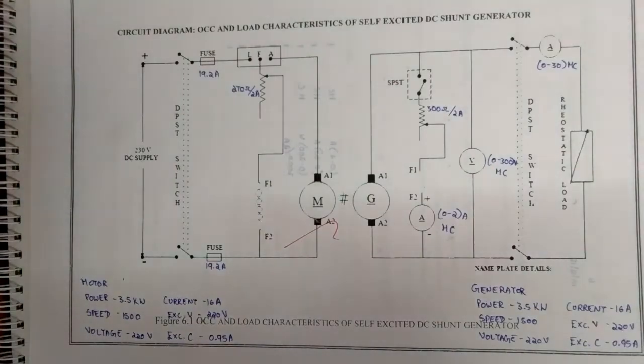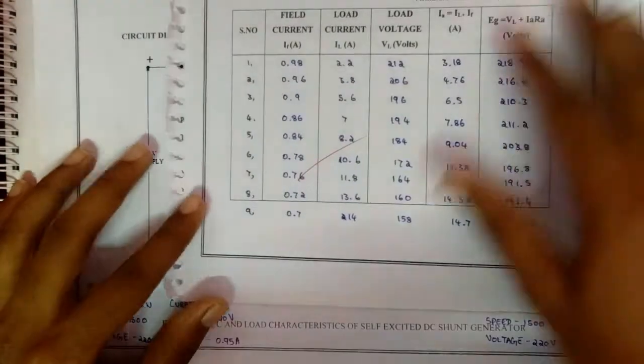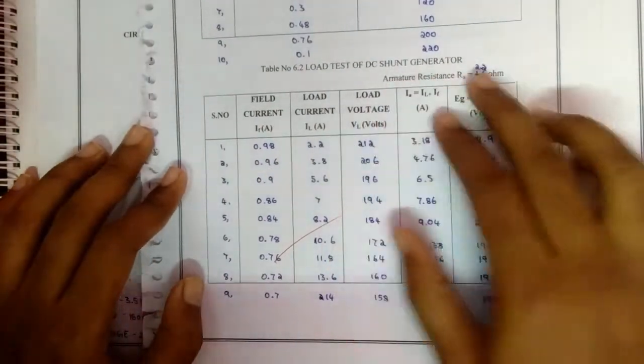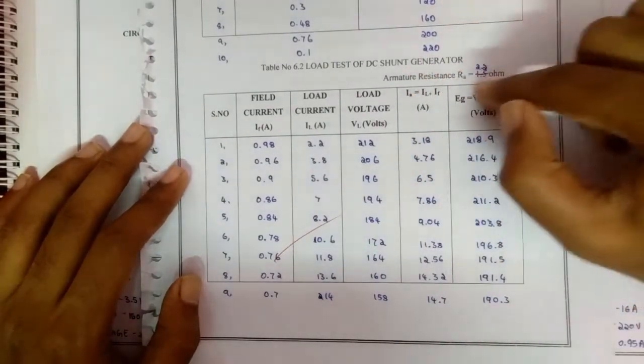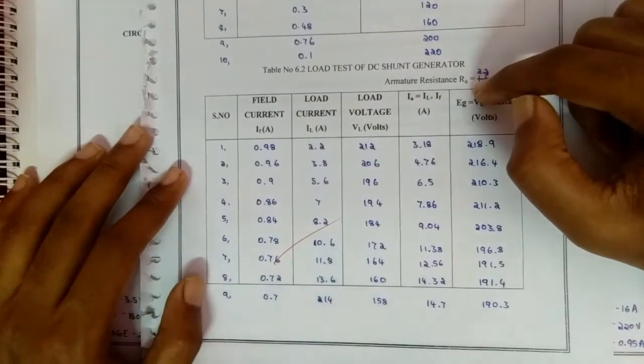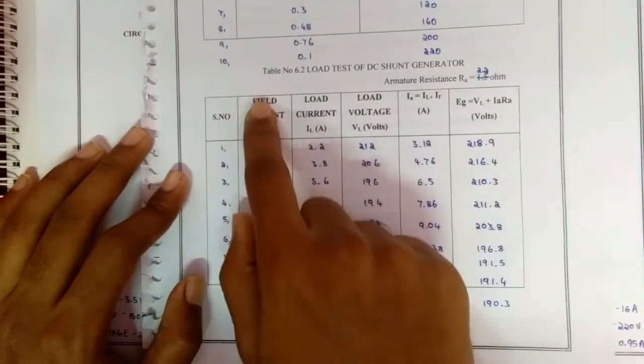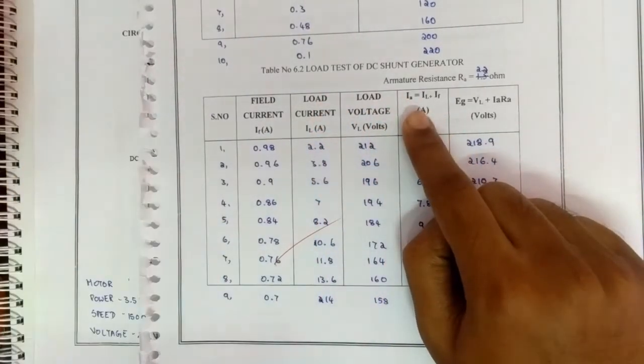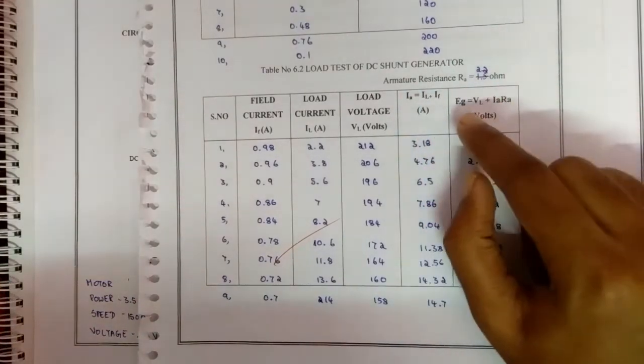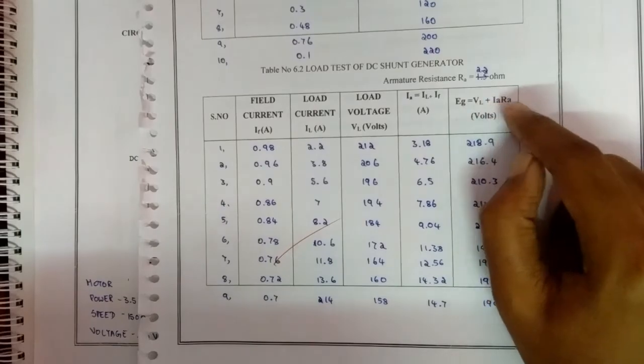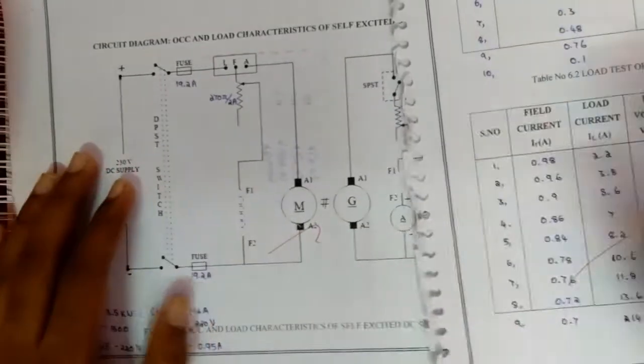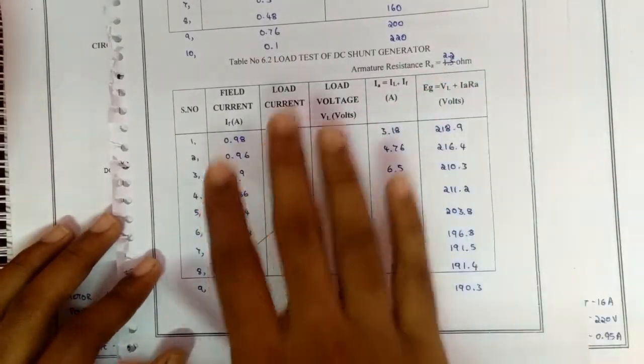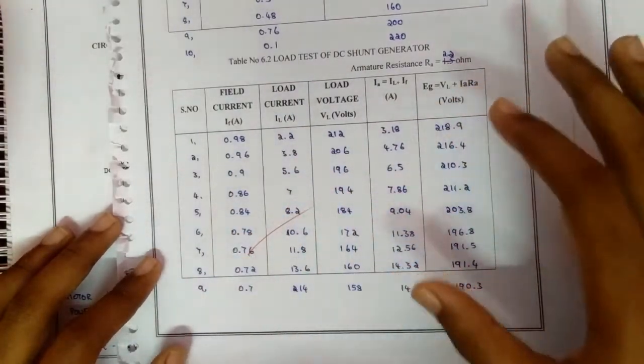The tabulation for the load test shows field current and voltage VL. I have calculated the resistance value using the multimeter. The tabulation columns will be field current, load current, load voltage, and armature current IA = IL + IF, and EG = VL + IA*RA. EG is the generated voltage. With this formula and these values we can find the value of EG.